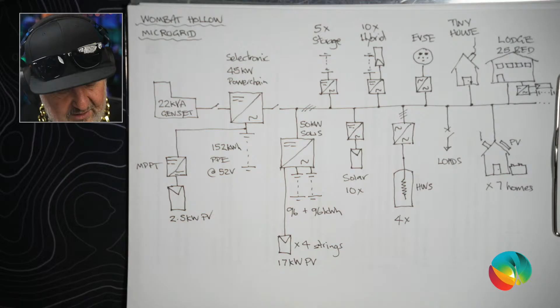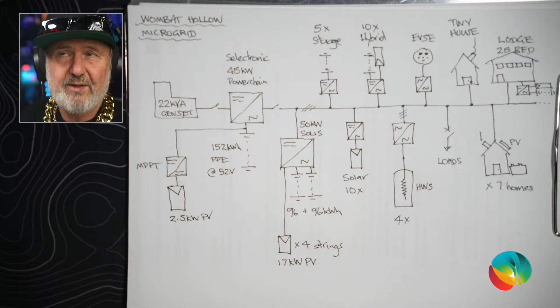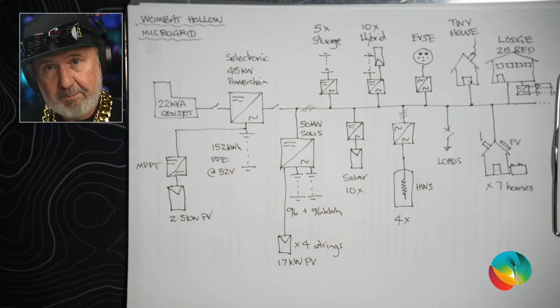So what you're looking at here is my really basic SLD of the Smart Energy Lab. And let's start at the beginning. We have a grid forming system. It's a Selectronic SP Pro. It's got 6 SPMC 482s, which are 7.5 kilowatt single phase inverters, 6 of them, but they're configured in 3-phase. That means 2 per phase, and that's referred to as a power chain in Selectronic speak. So that's our grid forming system. It creates the grid, and this is the grid here.